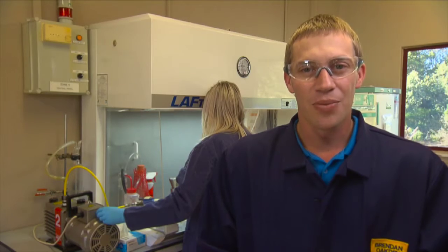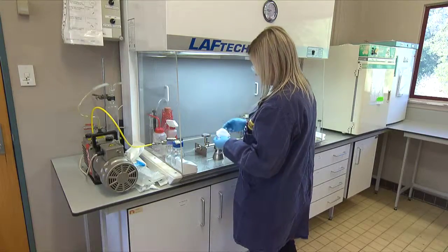So why test for microbiological contamination in fuels? Sulfate-reducing bacteria and other bugs can produce acid, which accelerates the corrosion process by chemically etching the metal surfaces of tanks and pipes, which in turn can lead to holes and pitting. Diesel bug can produce large amounts of biomass that can block filters and fuel lines, as well as causing accelerated corrosion in fuel tanks. So how do we do it?